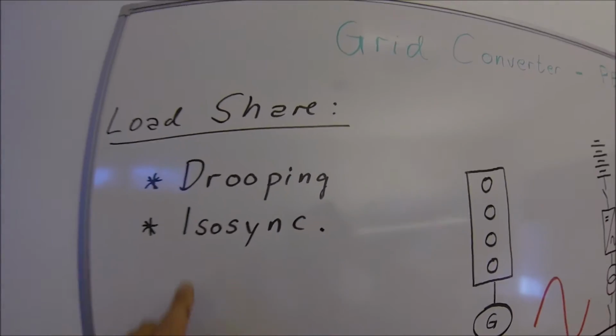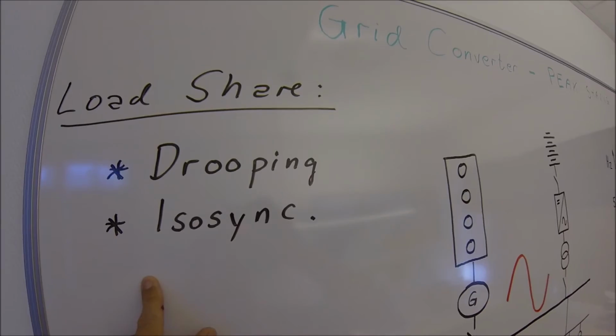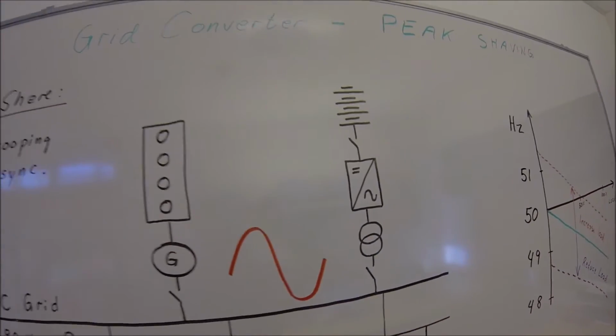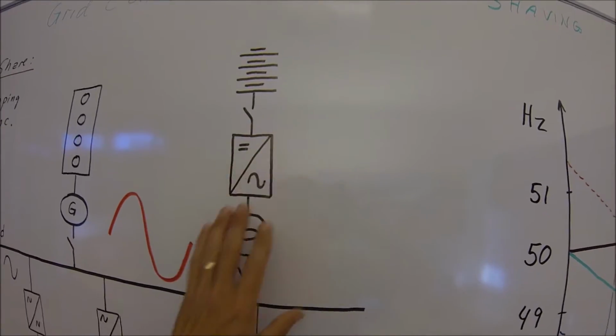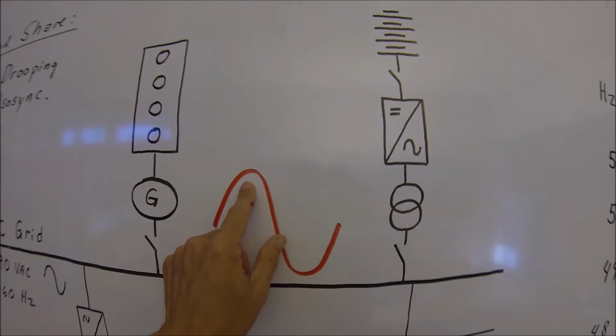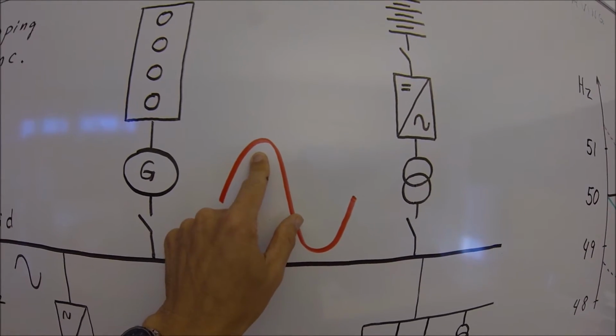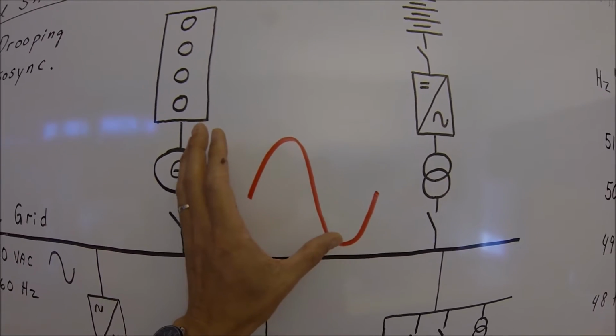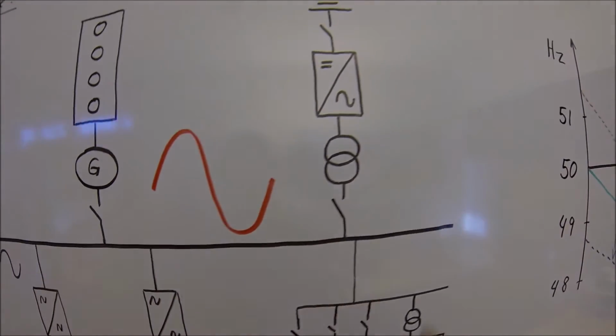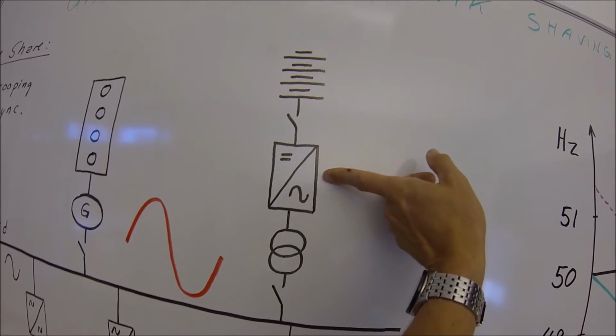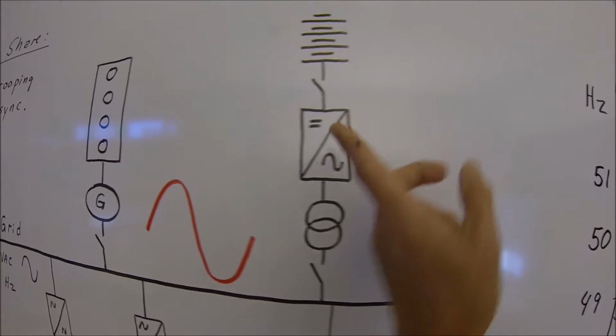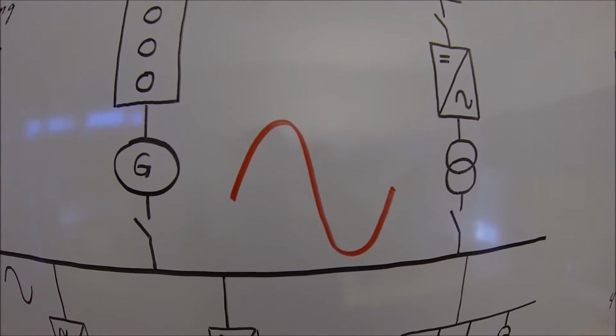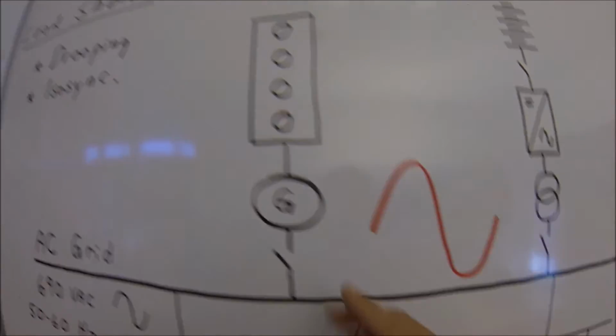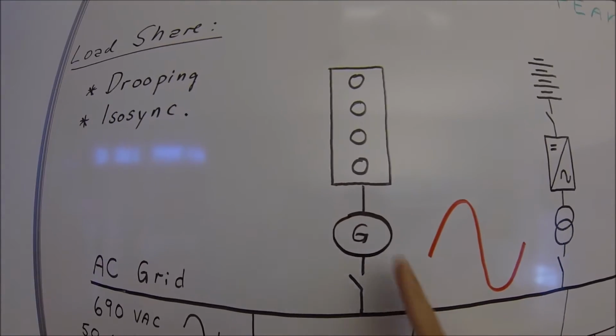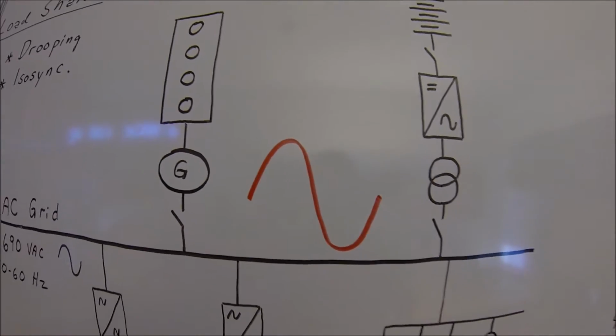What is the isosynchronous mode? Isosynchronous mode means that we just adapt to the grid on the ship and we adjust to whatever frequency is there. And if the reference says you are not taking any load right now, you will get the frequency which the other energy producers have created on the grid.